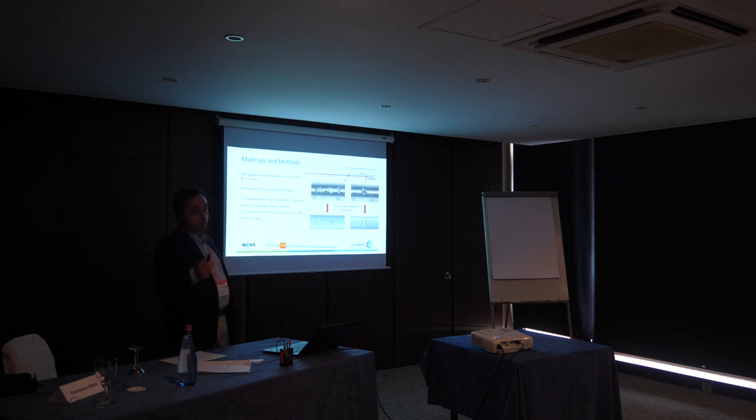In order to have a reference, we have also defined defects in an EQ wire with a diameter of 0.6 millimeter. Multiple defects were introduced 15 millimeters away from the tip, 1 millimeter in length, with the largest being 40 micrometers deep, and another single defect, 5.5 millimeters away from the tip, 0.2 millimeters wide and 100 micrometers deep.